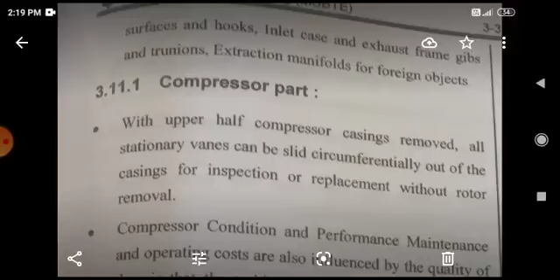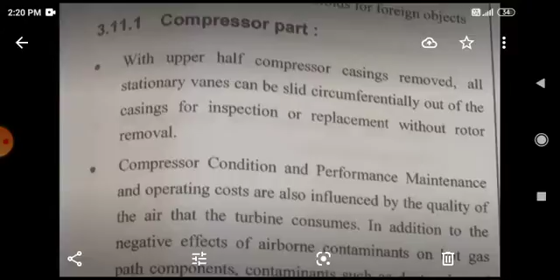Okay, next one is the compressor part. With the upper half compressor casing removed, all stationary vanes can be slid circumferentially out of the casing for inspection or replacement without rotor removal.